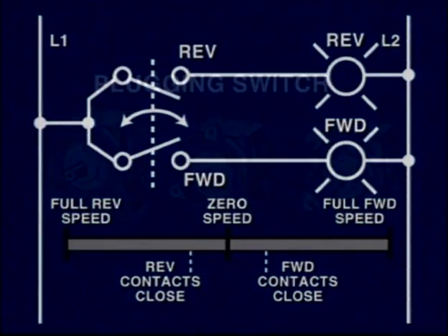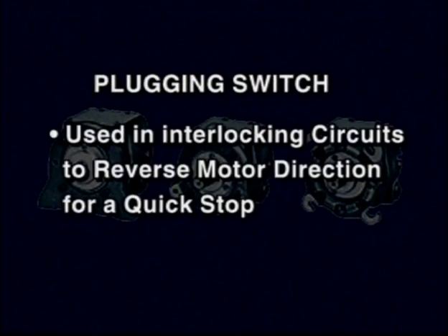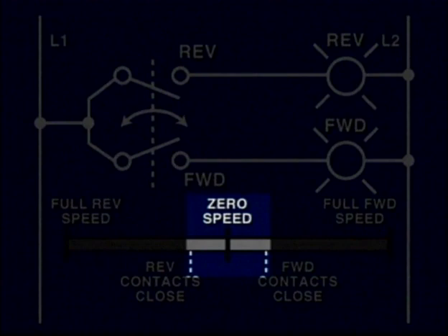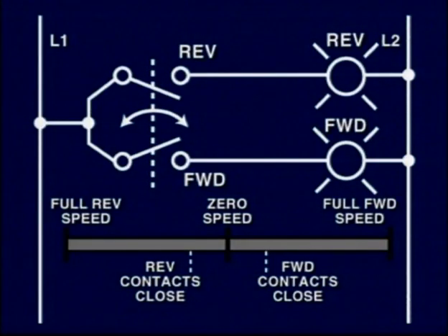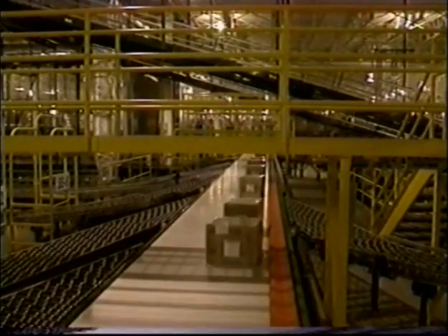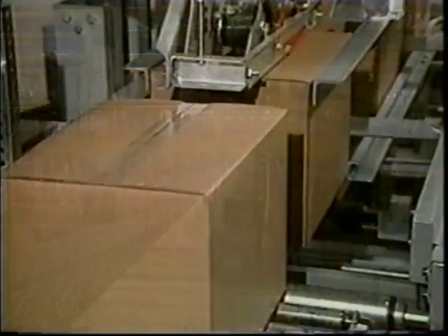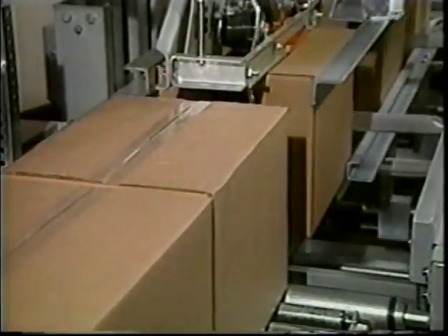The simple operation of the plugging switch is used in interlocking circuits whenever we want to stop a motor very rapidly by reversing the direction of the motor. When we reverse the direction, the motor will obviously stop faster because it is going backwards. This section of the switch will allow the control circuit to detect when the motor is almost at rest and disconnect the circuit which caused the motor to go in reverse. The use of this switch has many applications in conveyor systems where you may want to avoid the coasting of a motor carrying parts and would rather want the conveyor to go to a sudden stop. This also applies in emergency stop circuits where a motor would be brought to a fast stop when necessary.